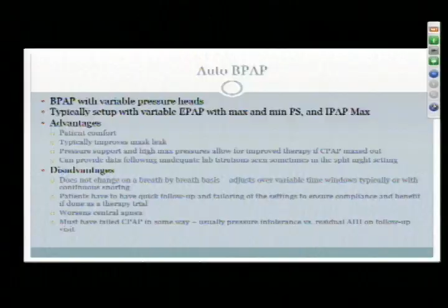All right, auto BPAP. So now we're getting really fancy. BPAP with variable pressure heads. Typically I set this up with a variable EPAP, so an EPAP min, an IPAP max usually of 25 because that's what the machine maxes out at, and then a pressure support max and min as well, so usually from 2 to 8, or if we've already seen that they need at least a pressure support of 6, 6 to 8, so there's some variance there.